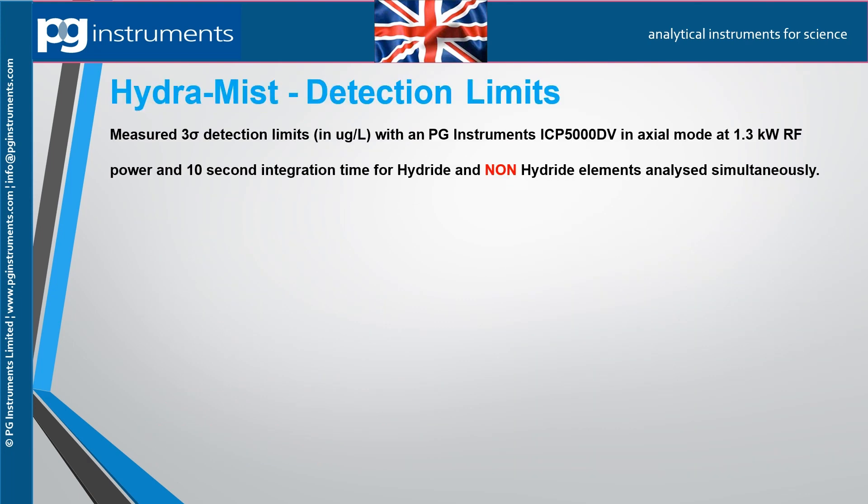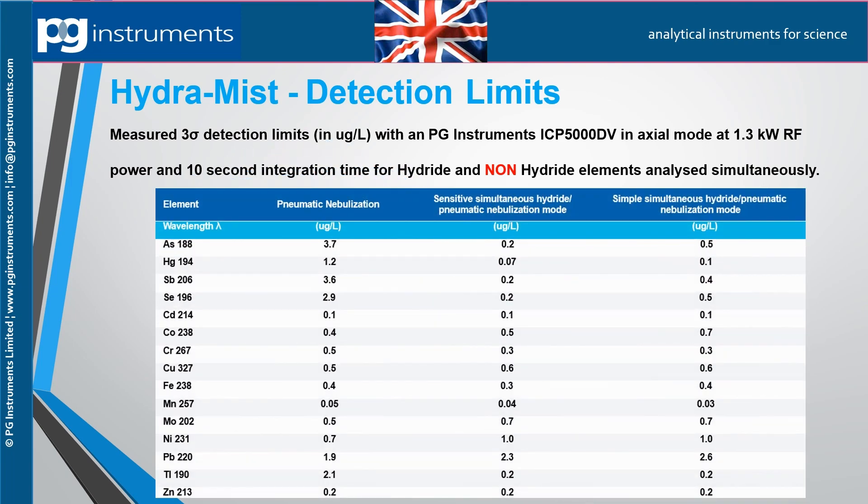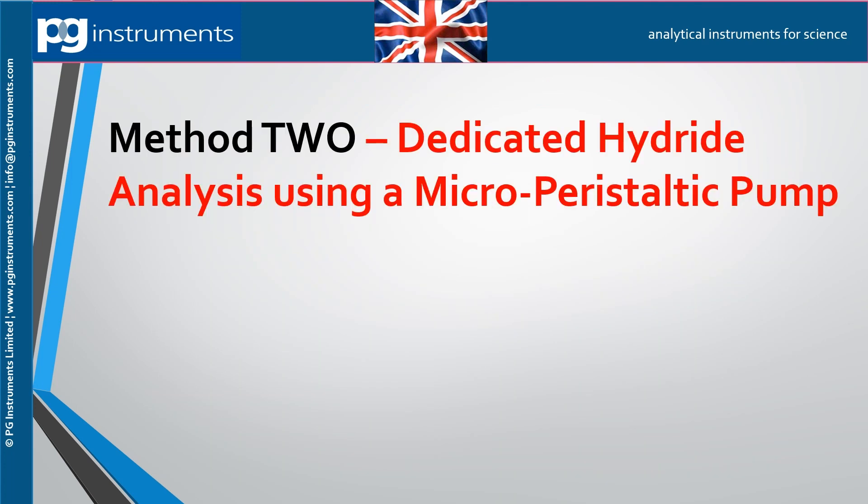Here are examples of the detection limits obtained using the Hydra-Mist. Measurements are made with the torch in axial view at an RF power of 1300 watts, showing detection levels for both hydride and non-hydride forming elements. Detection limits are shown in micrograms per liter in a water matrix.